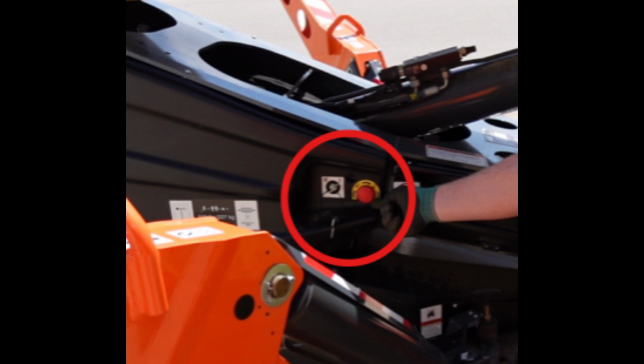Designed to European operation standards, the only way to completely remove power from the machine is via the key switch. The lower and upper emergency stop buttons simply tell the machine the operator wants to perform functions, or the operator does not want to perform functions. Neither e-stop will remove power to the system. When parking the machine, always make sure the key is in the off position.